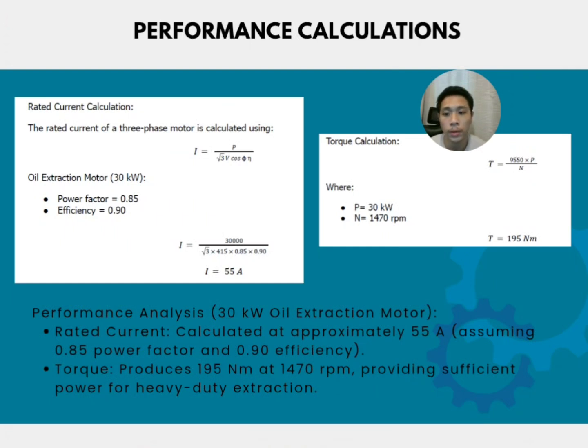Okay, moving on to my final part, which is the performance calculation. To make sure the system operates efficiently, we analyze the performance of the 30 kilowatt oil extraction motor. For the rated current, based on the formula stated, we calculate, and the motor shows an approximate current of 55 amperes at full load. For the torque output, using the stated formula, the motor generates 195 Newton meters of torque at its rated speed. Okay, the analysis: this high torque output at 1470 RPM ensures the system has sufficient power to handle heavy-duty extraction demands reliably. That's all from me.